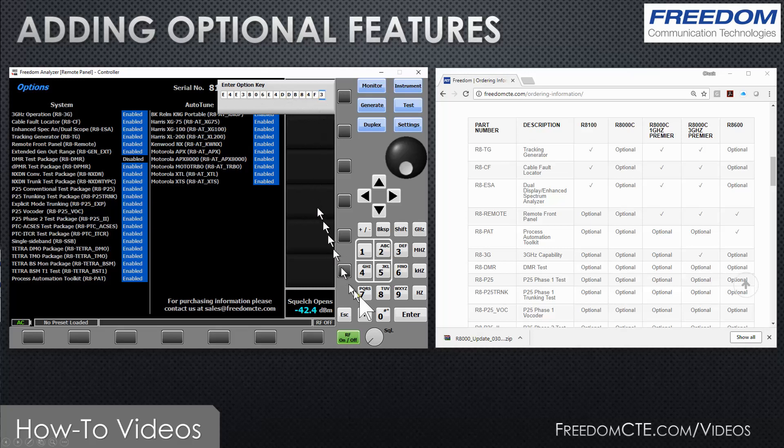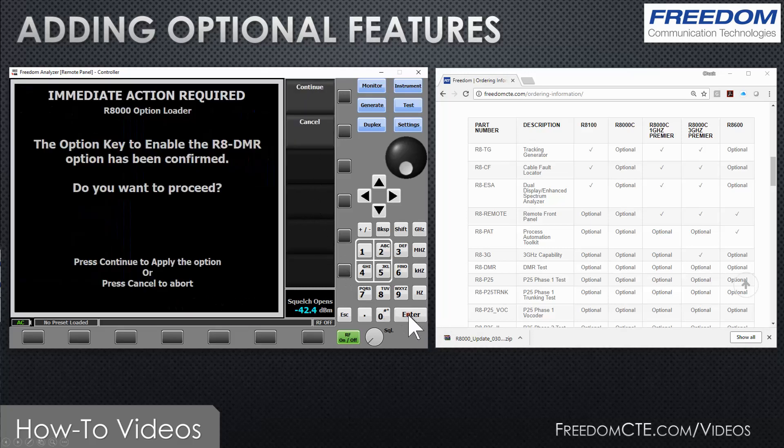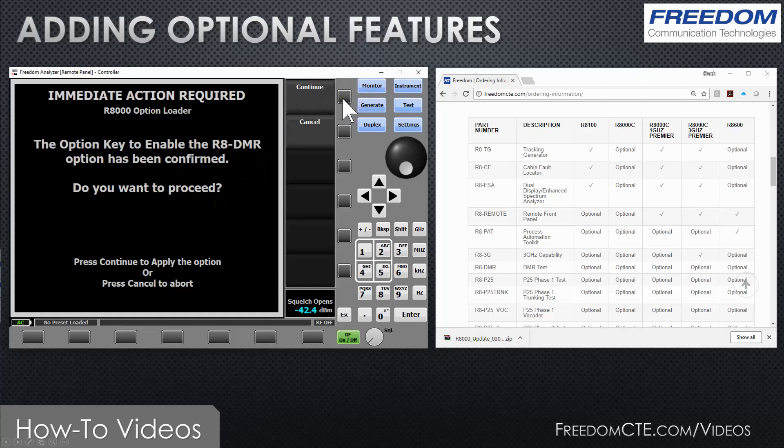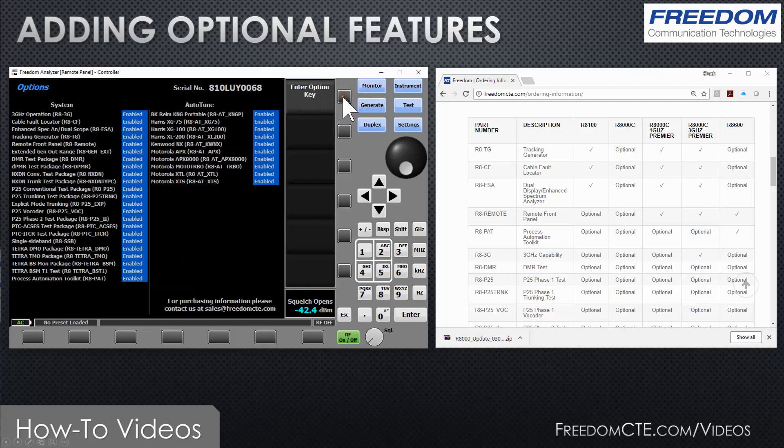Once you've pressed the enter key, the instrument will let you know if it recognizes it. In this case it says the option key to enable the R8-DMR, the DMR test package, has been confirmed. Do you want to proceed? In this case I do want to proceed and add this, and you will notice now it's added and I could start using it right away.